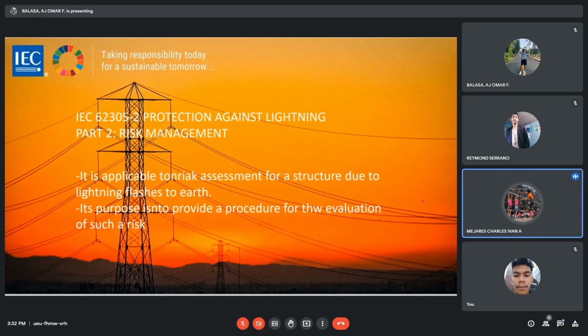IEC 62305-2: Protection against lightning, Part 2: Risk management. It is applicable to risk assessment for a structure due to lightning flashes to earth. Its purpose is to provide a procedure for the evaluation of such a risk. Once an upper tolerable limit for the risk has been selected, this procedure allows the selection of appropriate protection measures to be adopted to reduce the risk to below the tolerable limit.